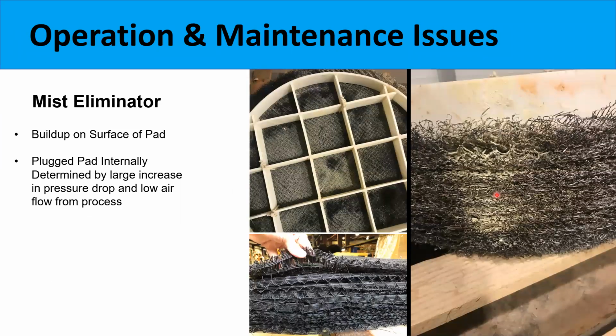The mist eliminator section, typically on the outlet of the wet scrubber, can either have a composite mesh pad or a vane style mist eliminator, like a chevron style mist eliminator. The vane type mist eliminators can handle and remove water droplets down to the 10 to 20 micron size diameter with about 99% efficiency, whereas these composite mesh pad mist eliminators can remove droplets down to around 1 micron size particles. And so, depending upon the application, we'll choose the mist eliminator accordingly.